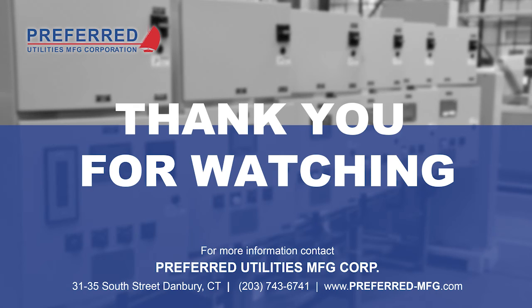Sometimes yes, sometimes no. I have seen pretty dumb fill stations that are just a cam lock fitting in a little enclosure on a pedestal, and that's it. If Preferred supplies a horizontal fill box, like what was in that picture with the fill truck, we will put an alarm horn and a light there that ties into the tank gauge to alert the operator when he's going to overfill the tank. The same is true of our sidewalk fill box that we didn't really show.